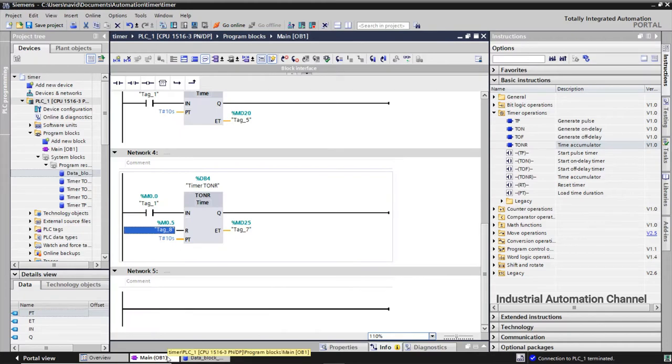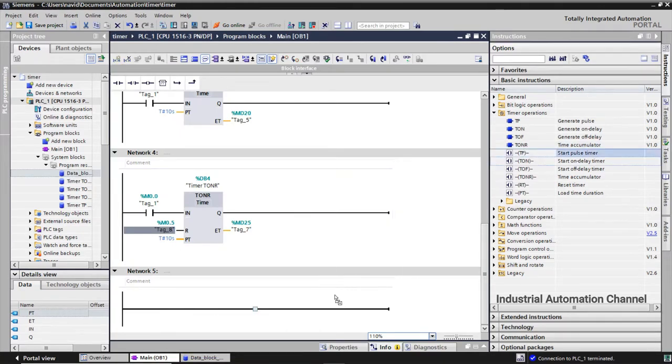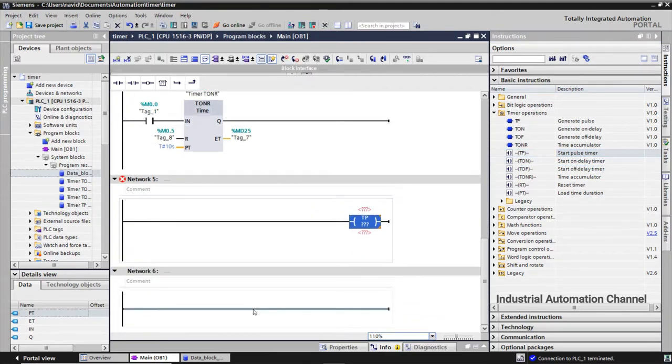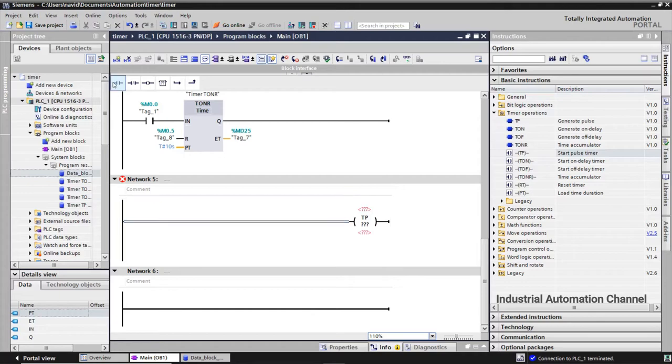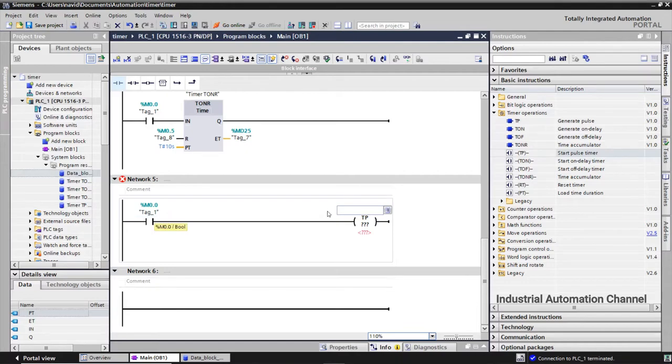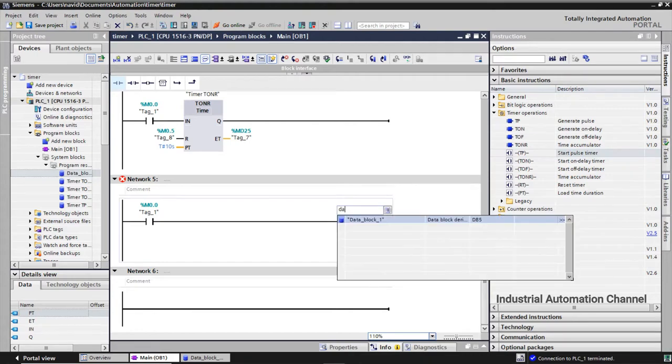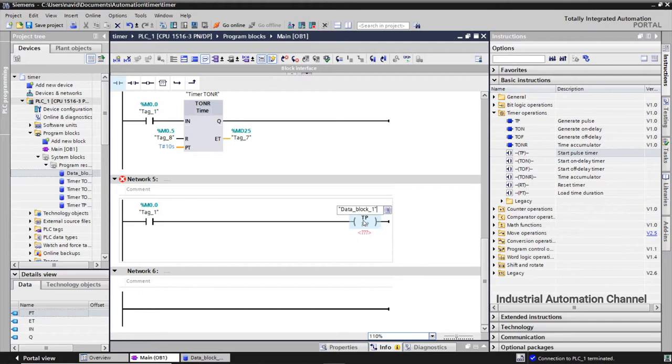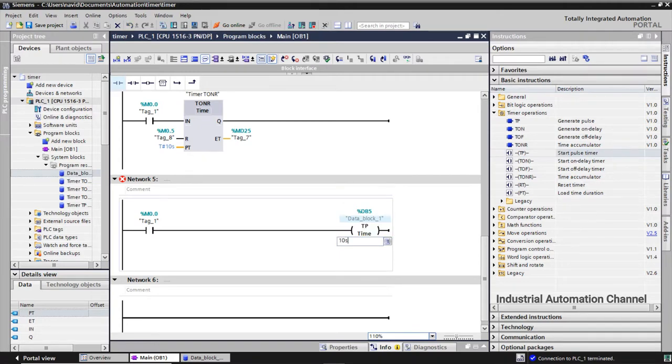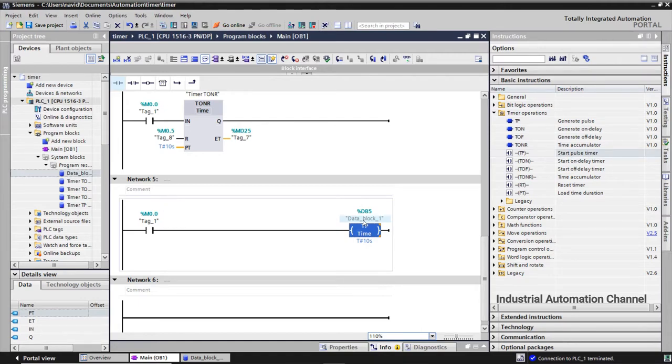Now let's insert one of the timers in coil type. I insert TP. Here we must write the address of the data block that we have created. If you write the first letter the address will appear here, click on it. Click again on none under the instruction. We write the time like block type. Now the timer is ready to use and it works exactly like the TP timer in block type.